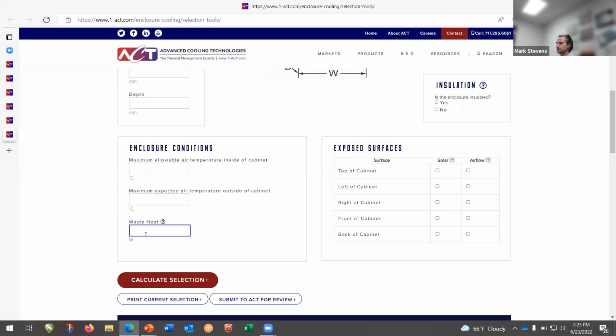Importantly, we're calling it waste heat here. This is the amount of thermal watts you believe your system is dissipating, not the electrical capacity of your cabinet, just the heat being generated on the inside. Most times you can calculate this number by adding up all the losses from the modules or devices populated in the cabinet. That heat value is input here so that we know how much heat we need to dissipate from your cabinet.